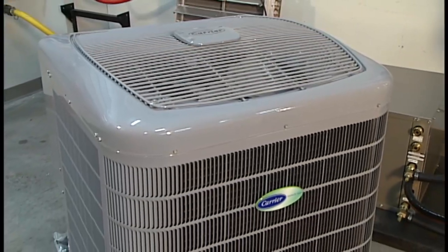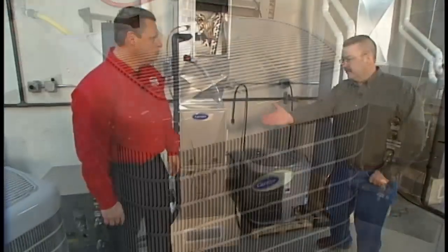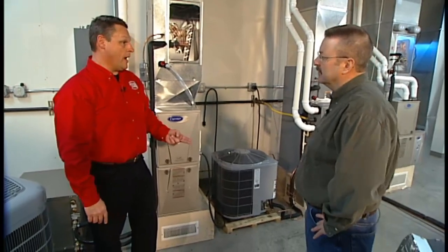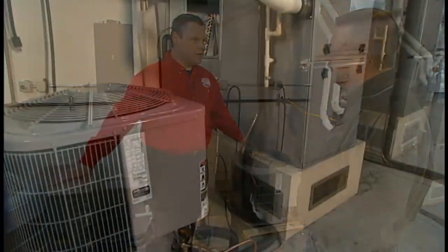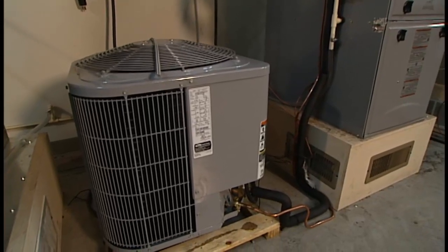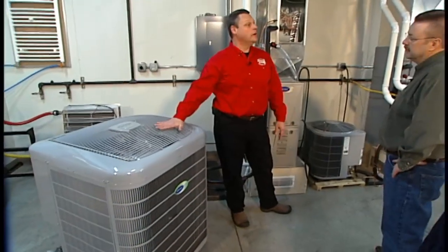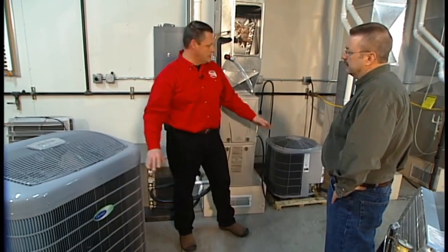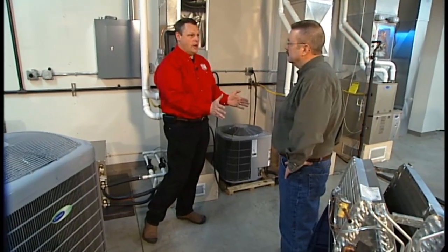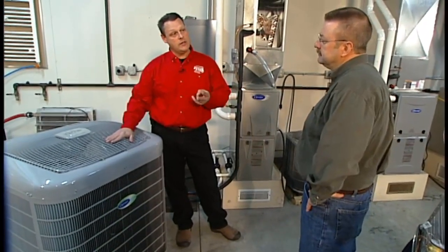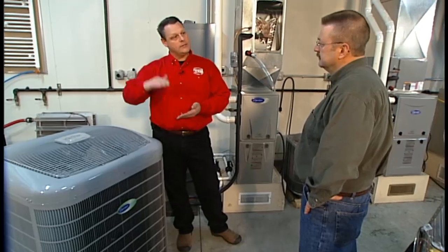Now over here there's a smaller-sized condensing unit as compared to this one here. Is it just based on the size of a house? Two things go into that. These are actually relatively close in the same capacity, but there's a difference in their efficiencies. This is a 13 SEER, this happens to be a 16 SEER. Another thing we have to consider is what we are doing within those cabinetries. This is an entry-level model, so it's going to be an on-off, 100% output when it runs. The advantage of this model as well is it brings us two-stage capacity through the compressor. Again, it's an upgraded model.